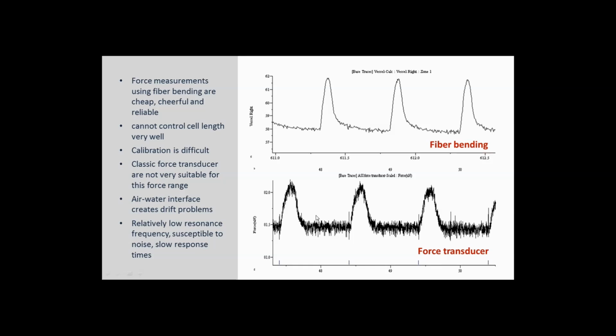Moreover, classic force transducers have an additional problem. They contain electronics. So you have a body of electronics, and then a stylus that sticks out of it, goes through the air-water interface, and sticks to the cells. Going through the air-water interface makes you very susceptible to external noise. And moreover, if the solution level changes, a change in buoyancy will change the force reading and greatly outweigh the force development of the myocyte itself. So you'll never be able to get a really stable force transducer.